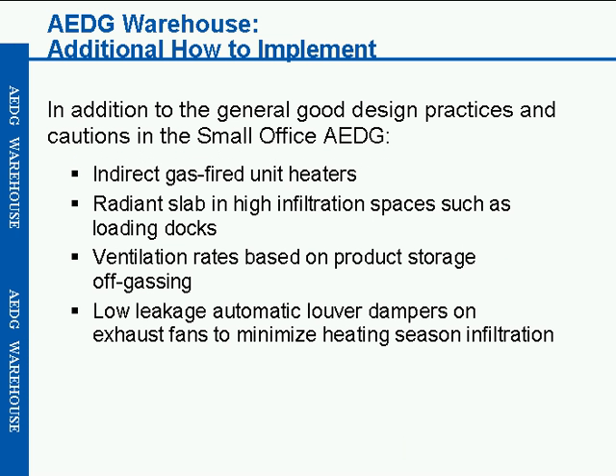So there are additional how-to-implement recommendations as well that are related to specific designs of warehouses. There are how-to-implement recommendations for things such as indirect gas-fired unit heaters, recommendations for radiant slab design in spaces that have high infiltration rates, such as loading docks, ventilation rates that can be determined based on product storage off-gassing rather than outdoor air requirements for people, as well as low leakage recommendations and design guidance for automatic louver dampers on exhaust fans in spaces that are not air conditioned, to attempt to minimize the heating season infiltration.